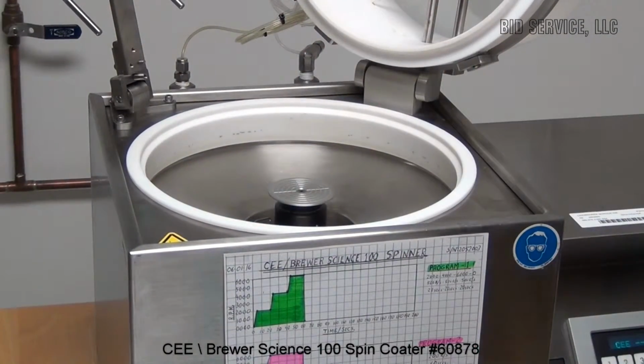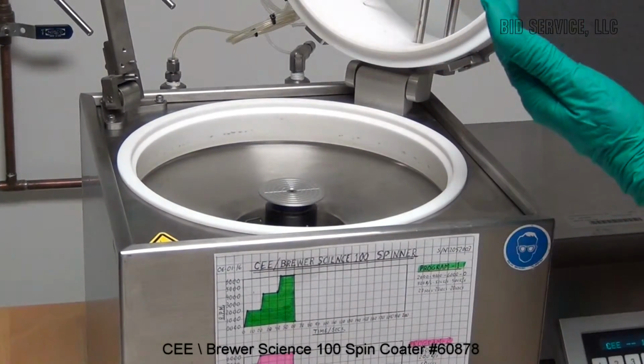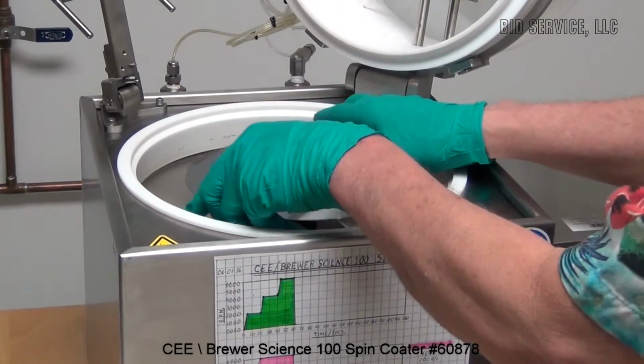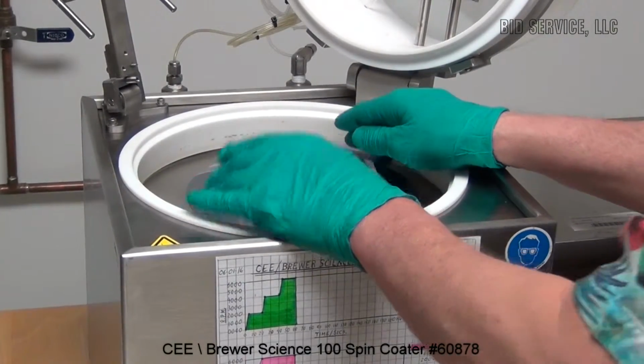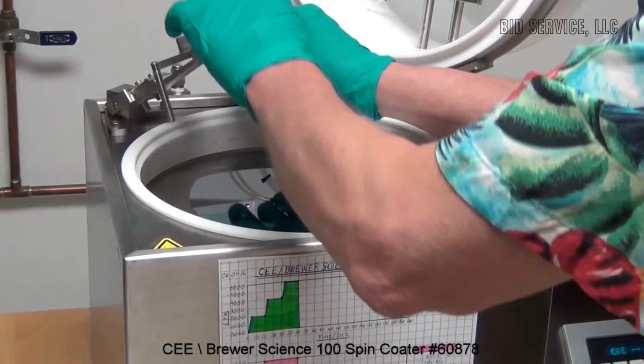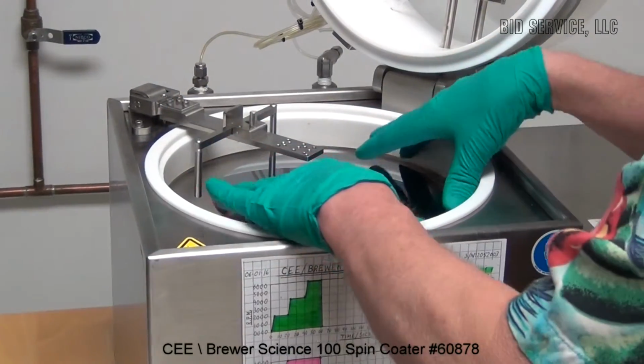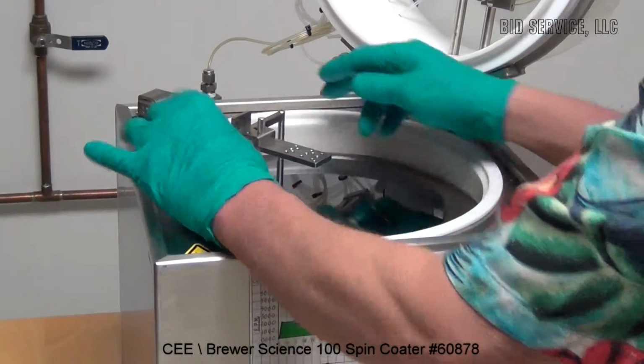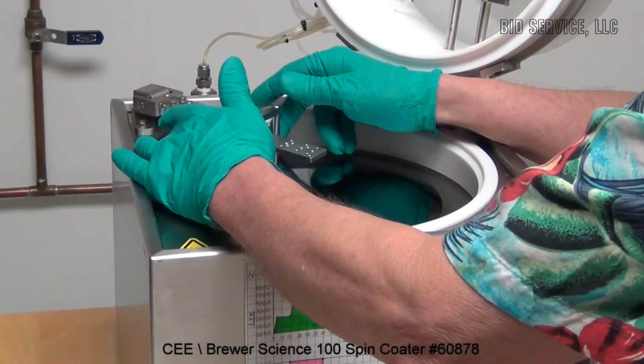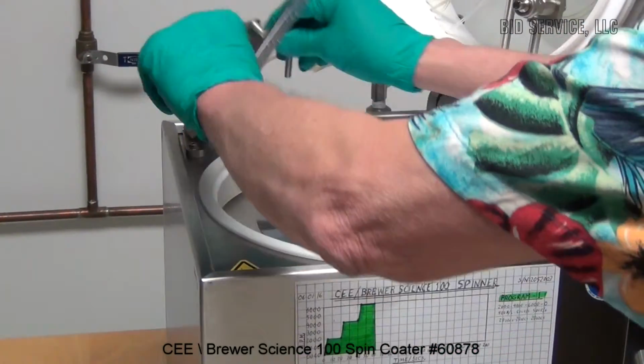Now, it has a nice mechanical feature. I'll give an example. Here is a 200 millimeter 8-inch wafer. When putting it on, and you can't tell where it's exactly centered, the centering arm is excellent. It comes down, and that will center your wafer. Now notice, when I put that on there, I push over all the way like that.